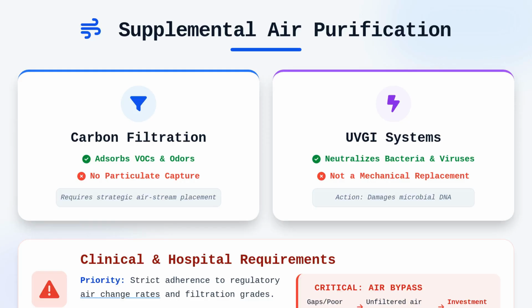When evaluating these systems for high-sensitivity environments like hospitals or clinical laboratories, the priority shifts toward meeting rigorous regulatory requirements that dictate specific air change rates and filtration grades. In such settings, even minor installation errors, like gaps in the filter rack or poor gasketing, lead to bypass, where air travels around the filter rather than through it. This leakage completely negates the investment in high-efficiency media, as unfiltered contaminants enter the supply airstream.